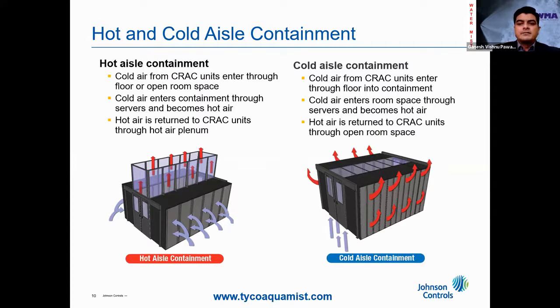And again, it is returned back to the CRAC units through the open room space. Now, when we are designing this water mist system, a sprinkler for a cold aisle will have a spacing of 3.6 by 3.7, or 3.6 by 3.6, or 4 meter by 4 meter, depending upon the approval. But when we consider it for the hot aisle, the spacing reduces to 1.2 meter by 1.2 meter.